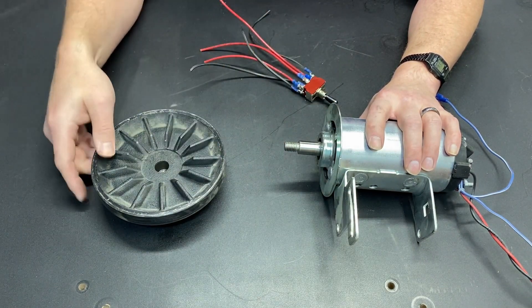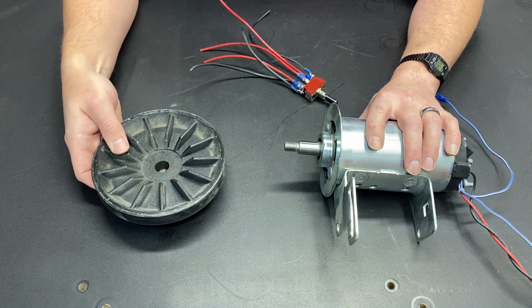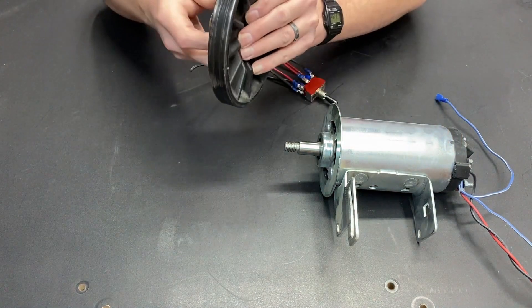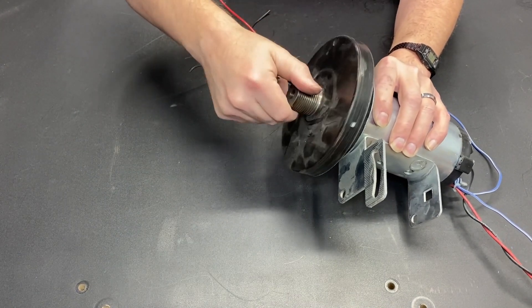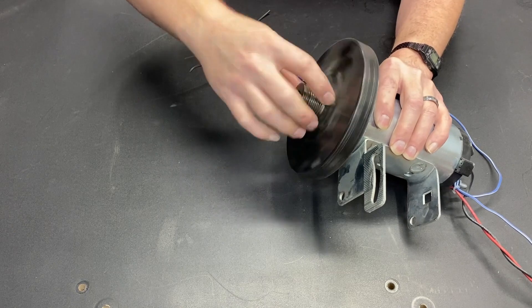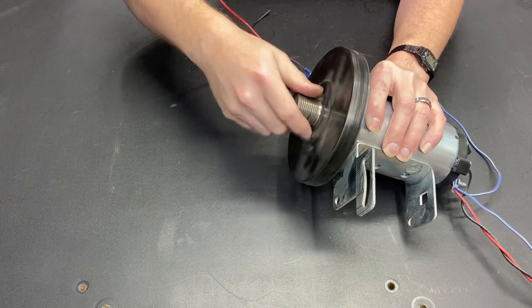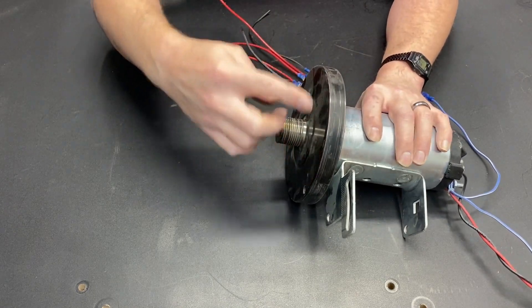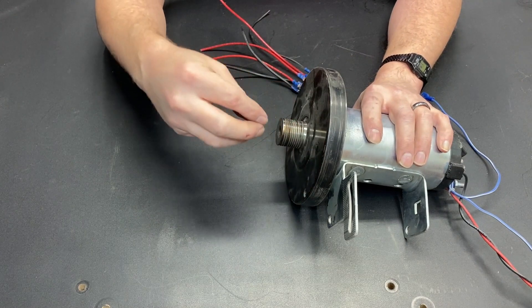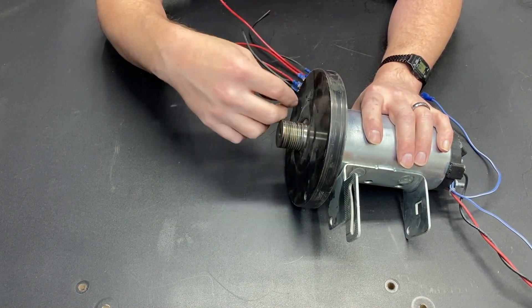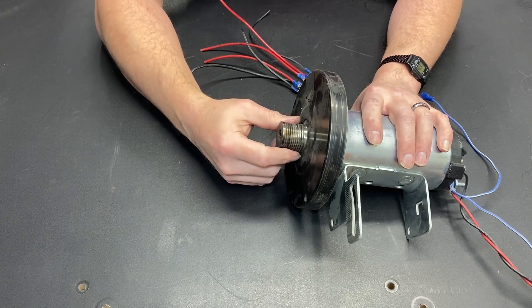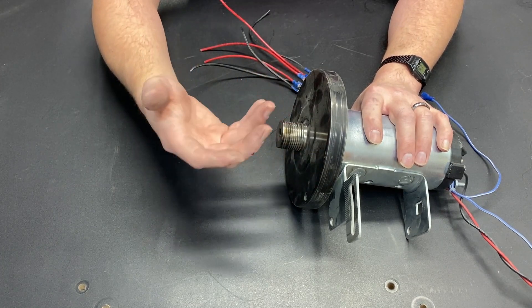This is a thread-on shaft. If we thread the shaft on, the motor goes clockwise like it's supposed to, those threads are going to stay tight. If we run it in reverse, this is going to spin off. And so, that can be a problem.